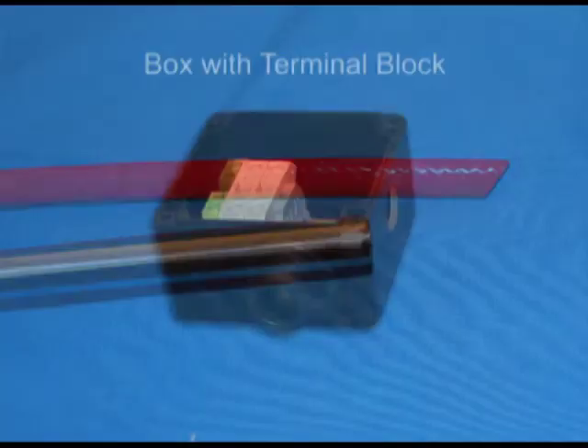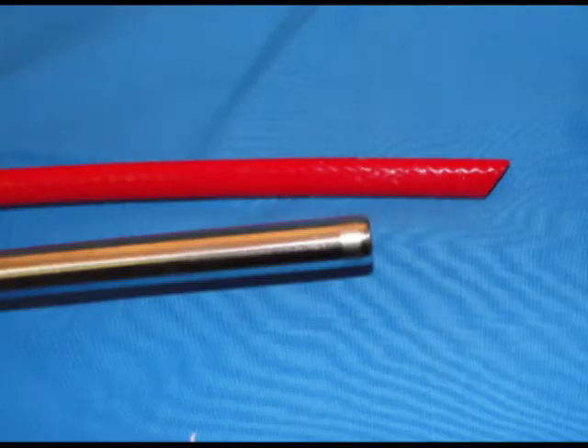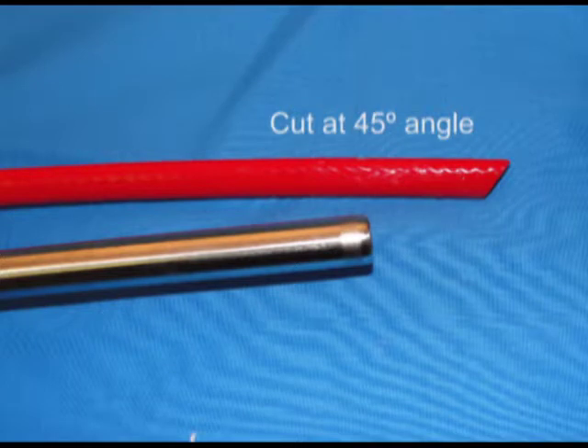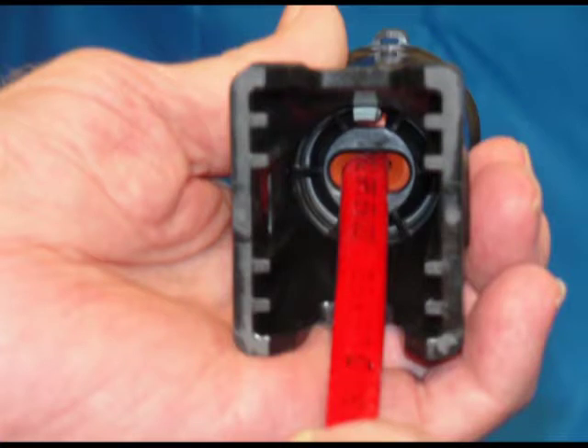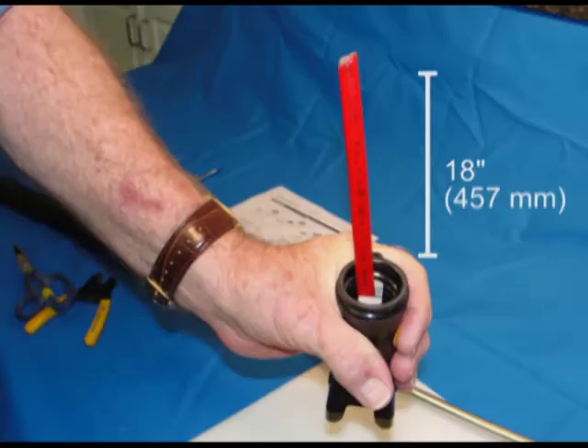Allow approximately 24 inches of heating cable for installation. Cut off heating cable end at about 45 degrees for easier insertion. With label on stand facing desired direction of box opening, push heat tracing through the bottom of the stand. Insert 18 inches of heating cable through stand. Use cable lubricant if needed.